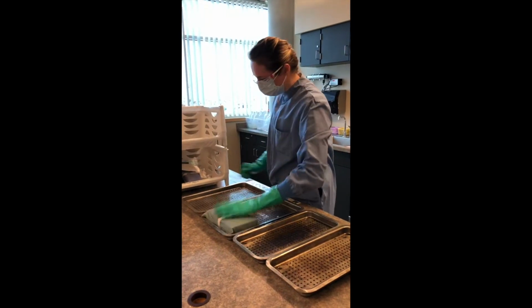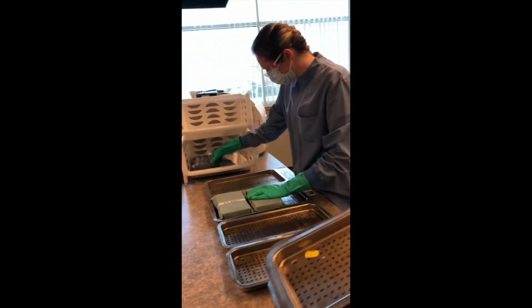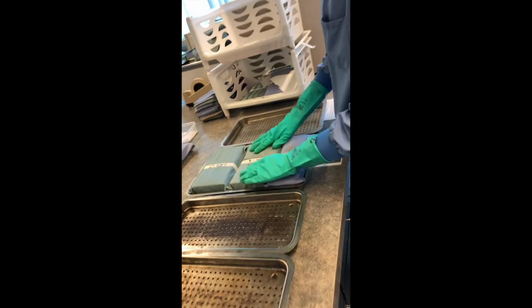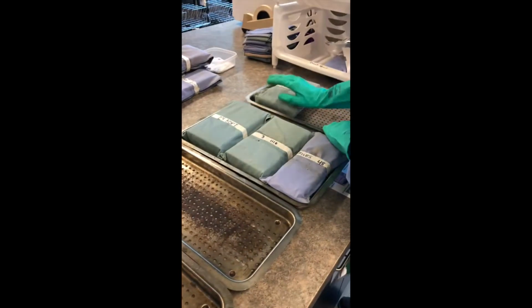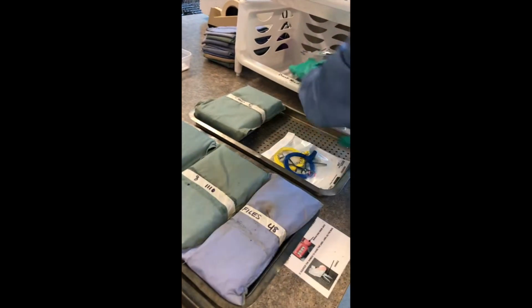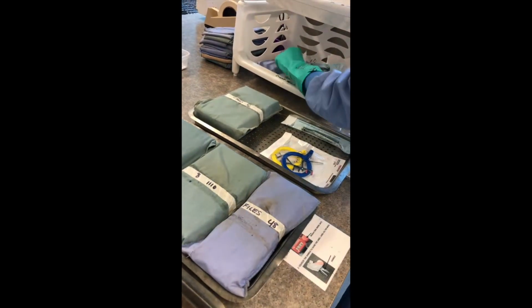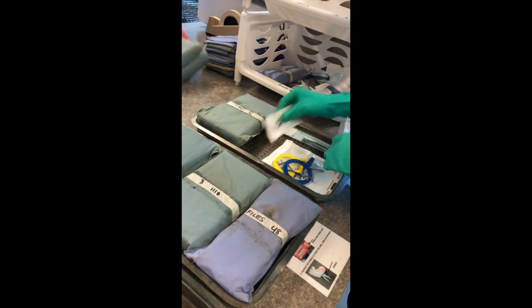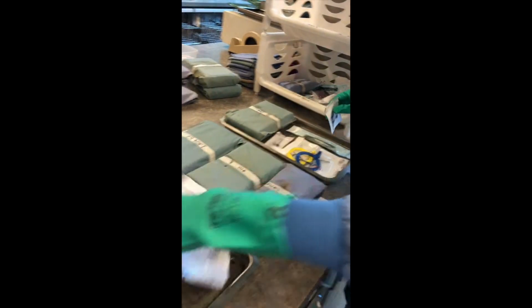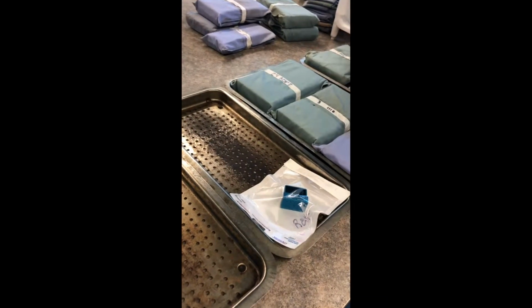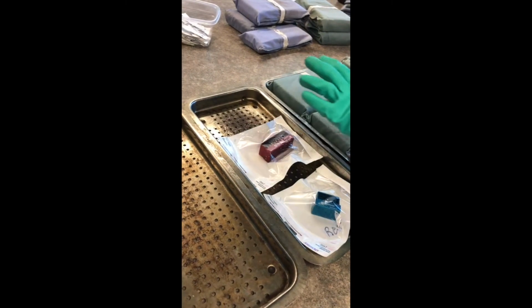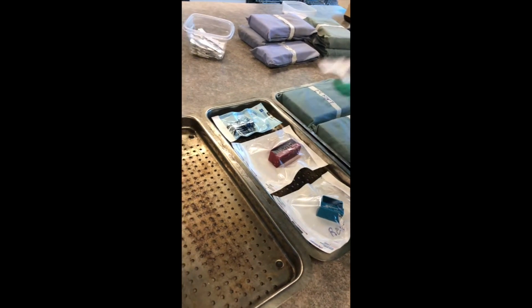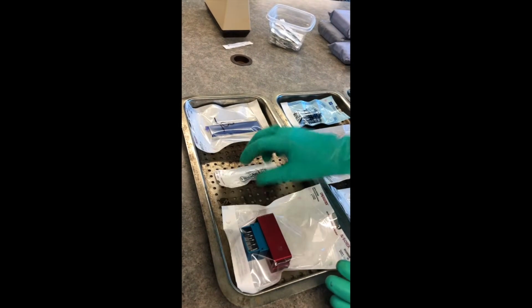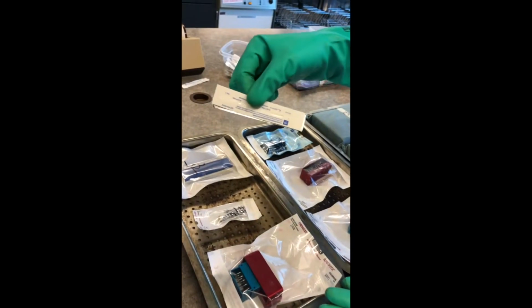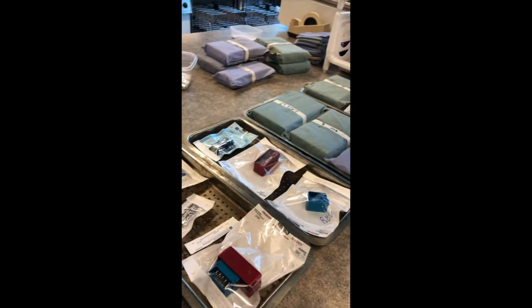The next step is to load the trays for the autoclave process. When placing instruments on the trays, make sure there is room between the instruments for air to flow through. Do not overlap instruments or pack trays too full. You should have about a finger's width of space between each instrument. After tray is full, place indicator strip on the tray.